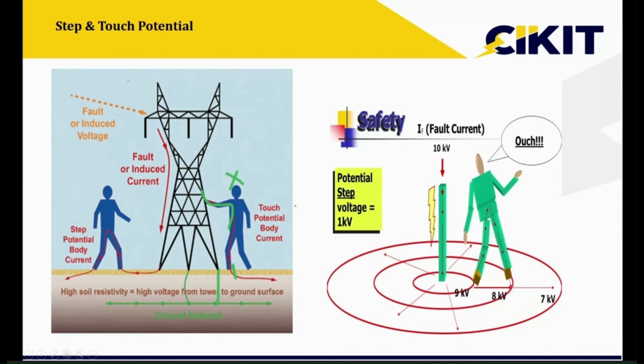And the second one is step potential. In this case, there is no need for direct contact. If the ground potential is increasing and there is a sufficient potential difference between the two feet, then because of the potential difference, current will circulate through the body and the person might get electrocuted. So the step voltage is very dangerous because there is no need for direct contact.